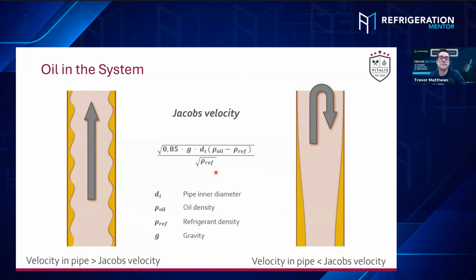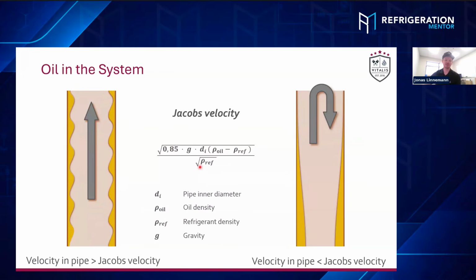It's on the outside of the pipes. Yeah. And maybe looking onto that formula, this formula is basically expressing the minimum possible velocity to return the oil. And there's basically just one number underneath here. So that's the density of the CO₂, of the refrigerant, and our refrigerant is CO₂. And we have learned that CO₂ density, vapor density, is very huge because of the relatively higher pressure. And that's the only number in that formula which is below that part. And this high density basically reduces the minimum needed velocity quite a bit.